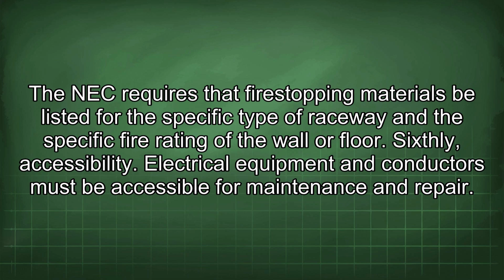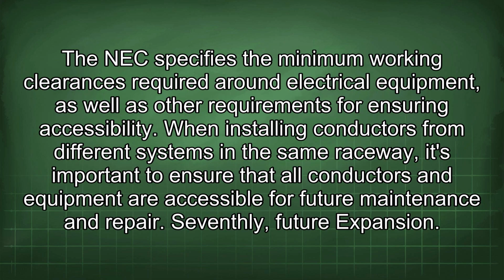Sixthly, accessibility. Electrical equipment and conductors must be accessible for maintenance and repair. The NEC specifies the minimum working clearances required around electrical equipment, as well as other requirements for ensuring accessibility. When installing conductors from different systems in the same raceway, it's important to ensure that all conductors and equipment are accessible for future maintenance and repair.